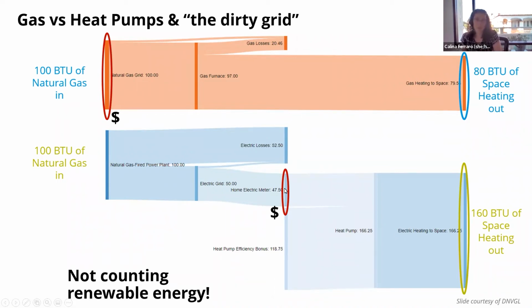The difference is that on site, we're using that electricity to drive a heat pump. So the heat pump uses that electricity to drive a compressor, which pulls the heat out of the air to put into our space or into the water. So we don't have to create that heat. What we're doing is using that compressor to pull this amount of heat out of the air. And that's where you'll hear people talk about a COP, or a coefficient of performance, for these compressors, which are usually somewhere between 3.5 to 4. That means that for every bit of electricity you're putting in, you're getting 3.5 to 4 times the amount of heat into your space from that.